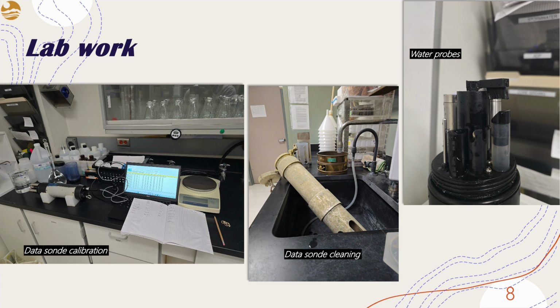After coming back to the lab, we'll first clean the sonde thoroughly using brushes and Scotch-Brite to make sure the sensor area is clean so the calibration won't be interfered with. We'll then download last month's data, calibrate and check the accuracy and response factor of all sensors, including pH, conductivity, turbidity, depth, dissolved oxygen, CDOM, and chlorophyll sensors with a variety of calibration standards. After calibration, we'll replace the battery, set up logging files, and reassemble the sonde for deployment.